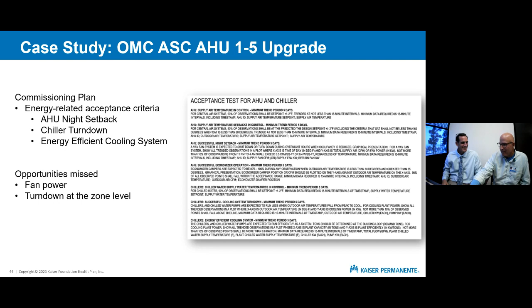This is really important when you talk about an air handler. The air handler can turn down, or the chiller can turn down, or the boiler can turn down, but if the demand out in the zones is constant, then congratulations, you just designed a system that's not actually ever going to turn down. Yeah, we were still flowing 1,500 CFM in each room. Exactly. So the first pass of commissioning did not validate any of the energy metrics.